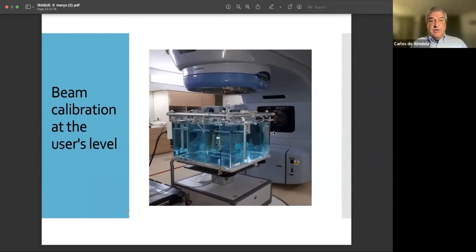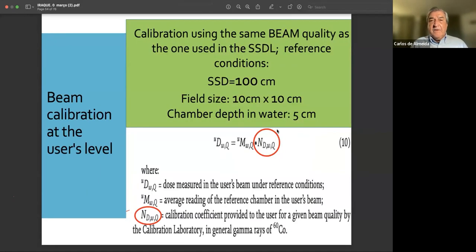Now, what we do in a beam calibration at our level is use a water phantom with a linear accelerator. Next slide. What we should normally do is use the same beam quality as the one used in the SSDL, okay? And use the same reference conditions: SSD 100, field size 10 by 10, and a depth of 5 centimeters.